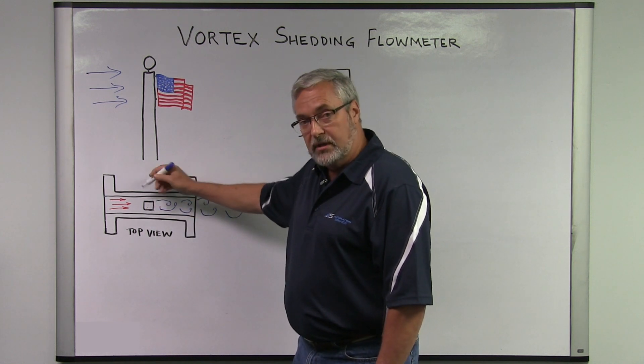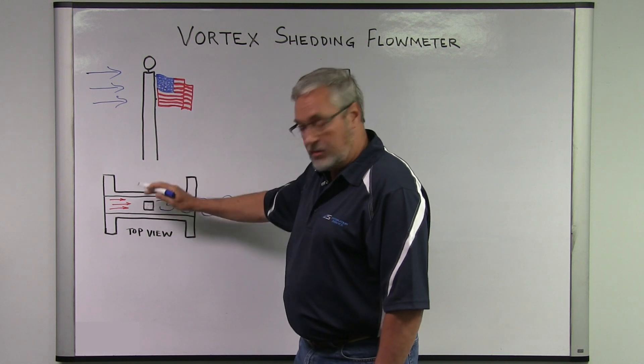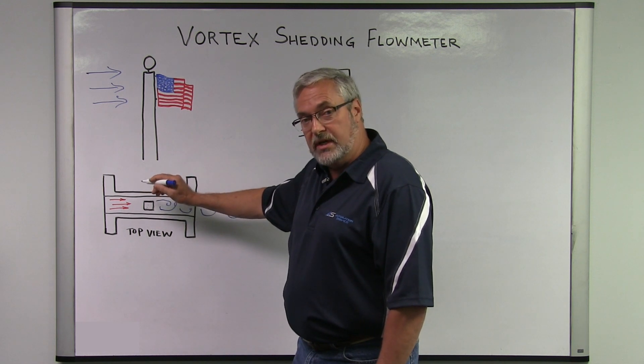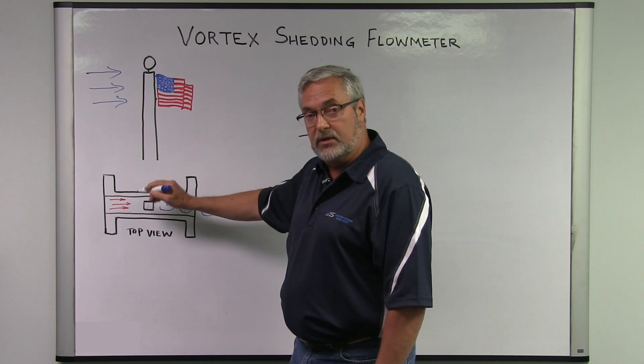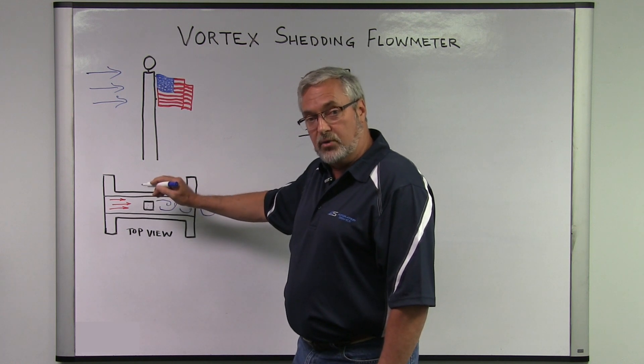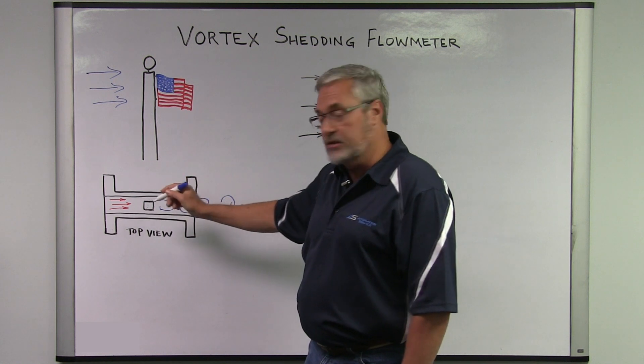The shedder bar has a piezoelectric crystal sitting on top of it. When the shedder bar moves back and forth — side to side in relation to the pipeline — it pinches those crystals and causes a change in frequency, which can be amplified and transmitted with a 4 to 20 milliamp signal.